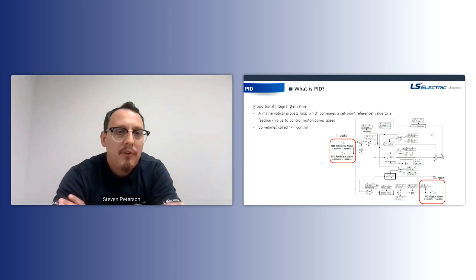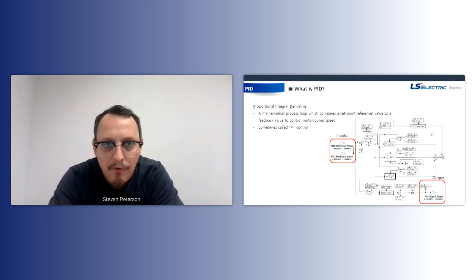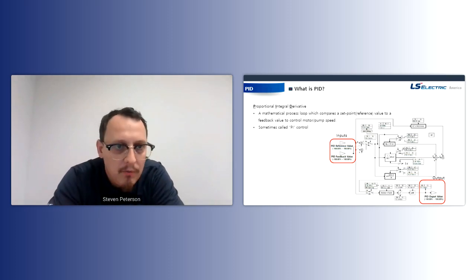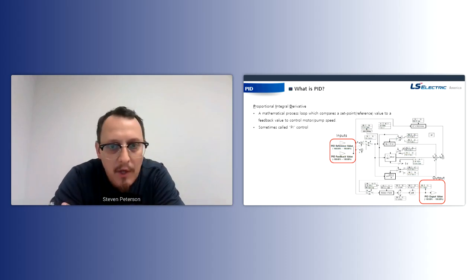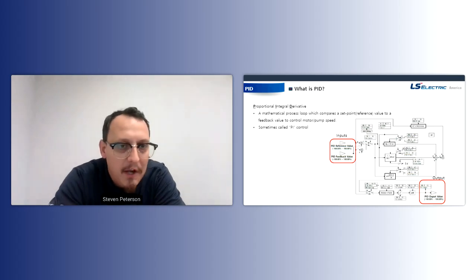What I'm going to explain next is a PID. So first off, what is PID? Well, PID is pretty much a process control loop, which is proportional, integral, and derivative. And a lot of times guys commonly just call it PI control because really you don't mess with the derivative too much. I've been doing this a while, and a lot of times I'm only adjusting the P gain and the I time. And if it's a bad day, then I'll be adjusting the derivative, but it doesn't happen too often.